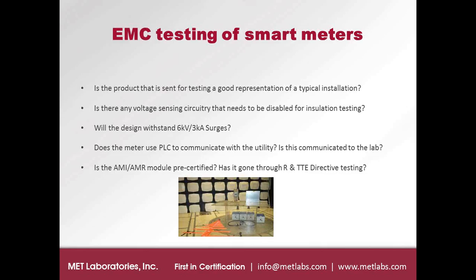So when you submit your product for testing, you need to be aware how your product is going to be installed, and you need to provide us with the adequate shielding, with the adequate enclosures that are representative of a typical installation. Because sometimes we just get a product wherein there are a lot of cables or bare wires coming out of the metering box and connected to CTs, and they do cause emissions and immunity failures.